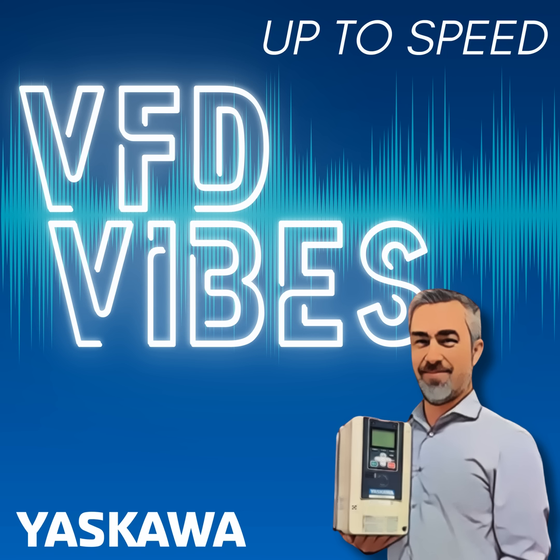Well, there's a toolbox available, Greg, and thank you for mentioning the subject. When you talk about just a drive with no mitigation, that drive will produce upwards of 90% THDI. That's your total harmonic distorted current. I want to clarify, you mean a standard 6-pulse drive. Standard 6-pulse drive, your standard off-the-shelf VFD from Yaskawa or any number of suppliers will perform about the same without any form of mitigation. The first line of defense is to add inductance. So what's inductance? Well, an inductor, which has inductance, is an electrical component that resists changes in current.